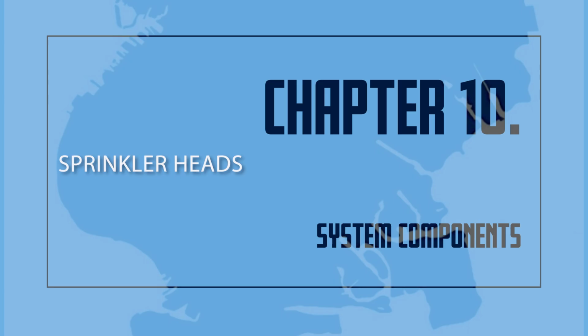Some sprinkler heads are designed to be used in special situations. Sprinkler heads exposed to corrosive conditions are often covered with a protective coat of wax or lead. Corrosive vapors are likely to make automatic sprinklers inoperative or slow down the speed of operation. They can also seriously block the spray nozzles in the sprinkler heads. They can damage, weaken, or destroy the delicate parts of the sprinkler heads. In most cases, such corrosive action takes place over a long time. For this reason, the sprinkler heads must be carefully watched for signs of corrosion. Care should be taken to make sure that the protective coating is not damaged when handling or replacing the heads.